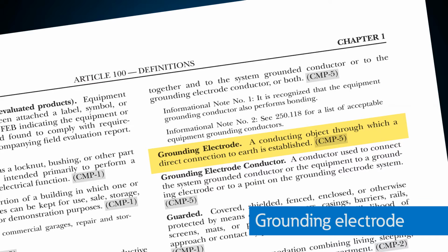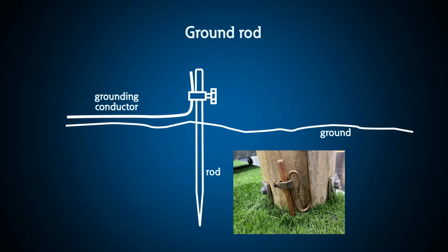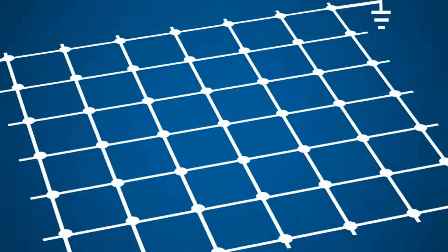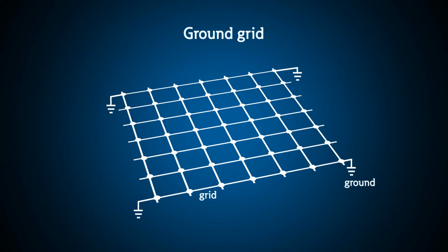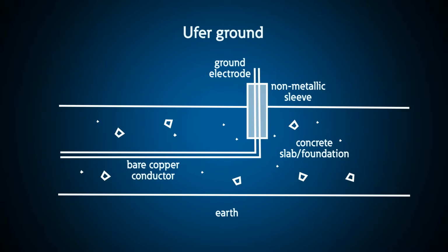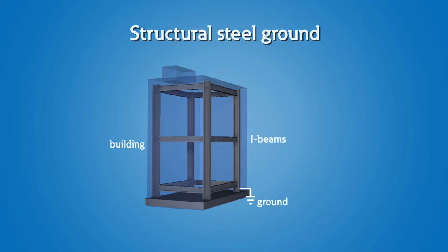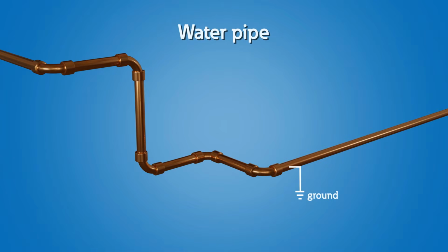So a grounding electrode is a conducting object used to make a direct electrical connection to the earth. This is typically your ground rod, a very common solution with regard to your grounding electrode. It could be your grounding grid, it could be the Ufer ground, or inside of a building it could be the structural steel or the water pipe coming into your home. Those are all grounding electrodes. And you could have multiple grounding electrodes at any one installation.